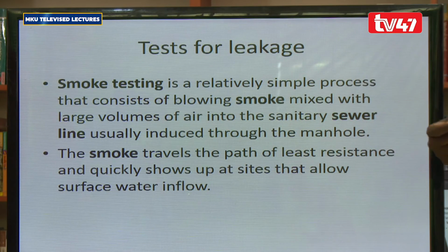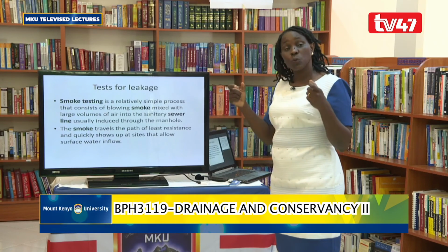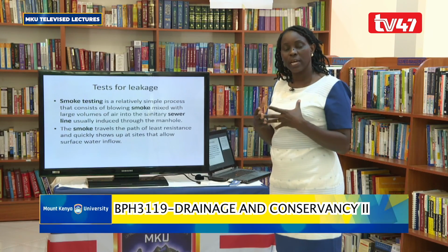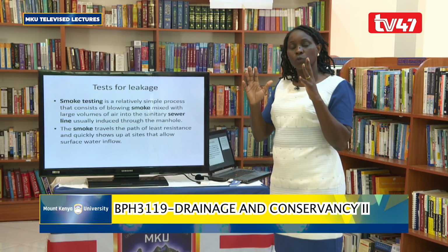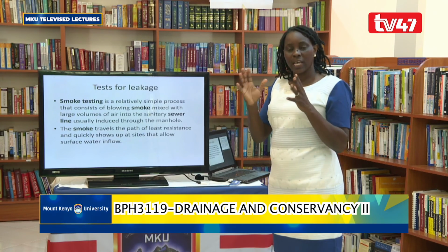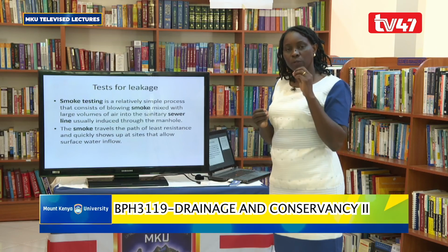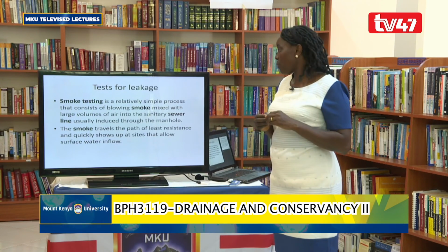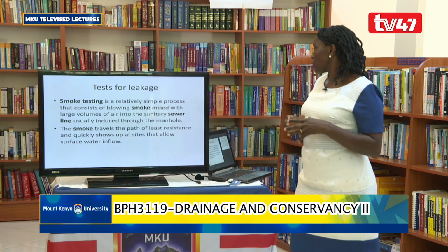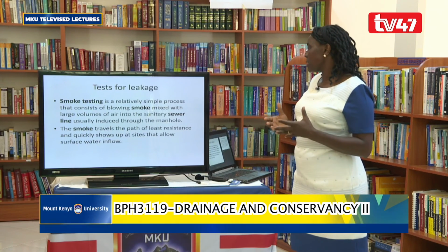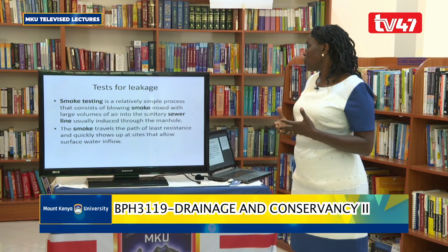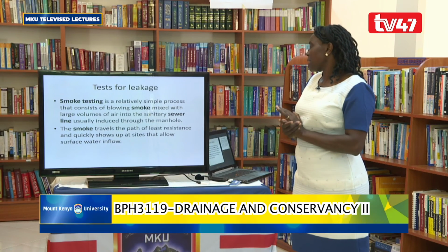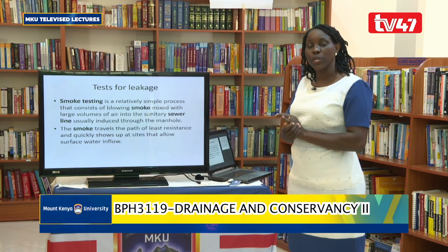You blow air inside with smoke, and if there is leakage on that pipe, you will be able to see smoke on the surface. Therefore, where there is smoke, you know that water is likely to leak from there. The smoke travels through the path of least resistance and quickly shows up at sites that allow surface water to inflow.